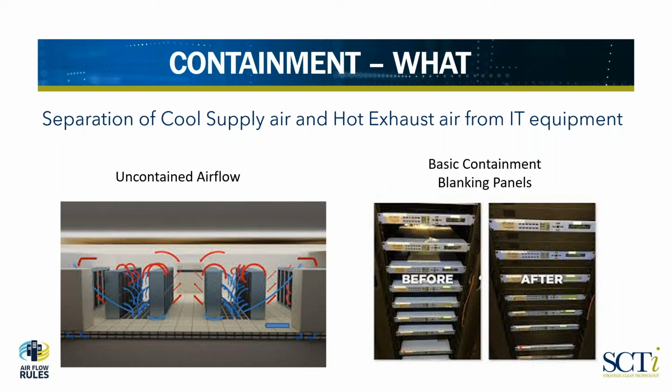Arnold, I would add that sealing the floor goes hand in hand, that first level of blanking cabinets, but also sealing the floor. And I'm sure many of you recall the days when you had a 6-inch by 8-inch hole in the rear of your rack on the floor and just blowing cold air into the hot aisle.